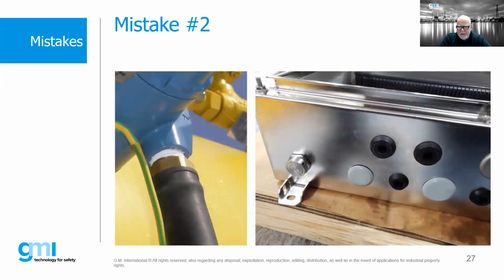So a couple other things that we see that are pretty common. The box on the right-hand side, these are a couple that I've done where we see a combination of maybe certified stopping plugs, and then we see things like maybe either traveling plugs or in this case, non-certified plugs. So we have to make sure that the components that we're putting on the outside of our EX equipment matches the protection concept of the equipment itself.